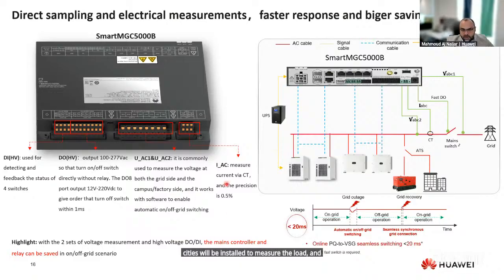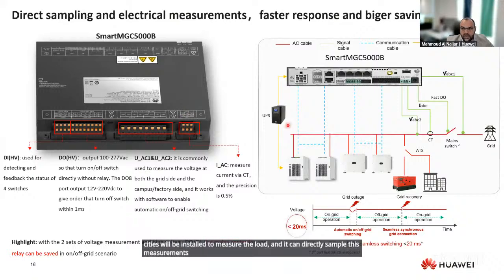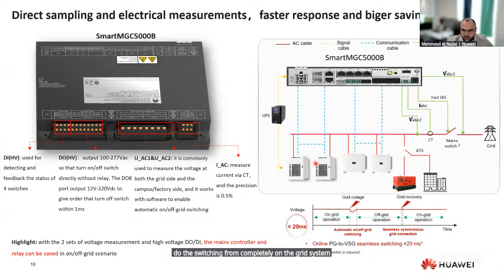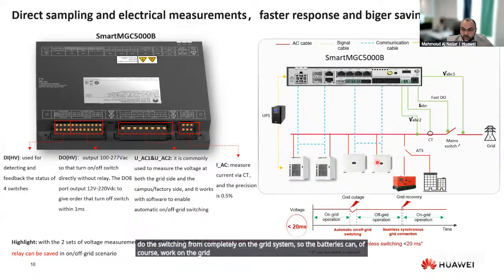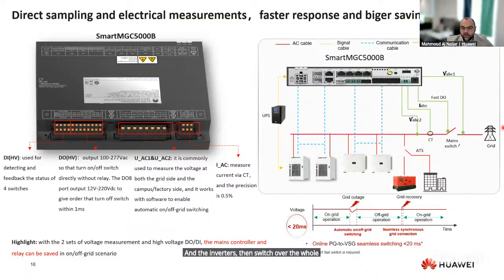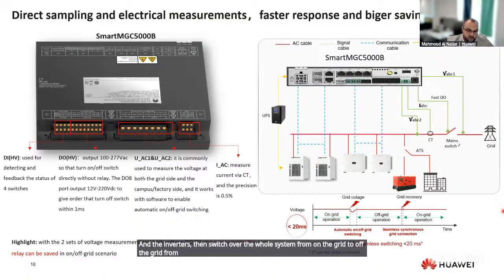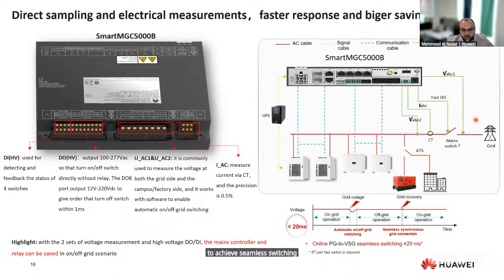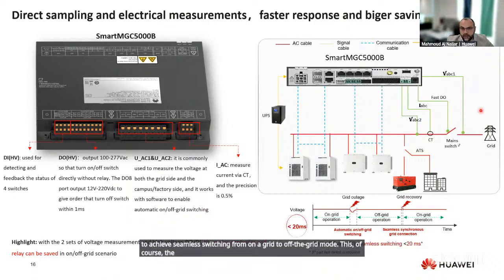And it can directly sample these measurements to the controller. It can sense the voltage to see if there's any power interruption, then directly do the switching from completely on the grid system, so the batteries can of course work on the grid, and the inverters then switch the whole system from on-grid to off-grid and from PQ to VSG mode in less than 20 milliseconds to achieve seamless switching from on-grid to off-grid mode. This is, of course, the fastest switching in our industry, to make sure you have smooth operation in case there's any power interruption. This is for on-grid application.